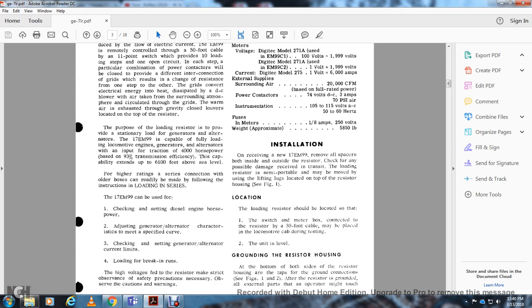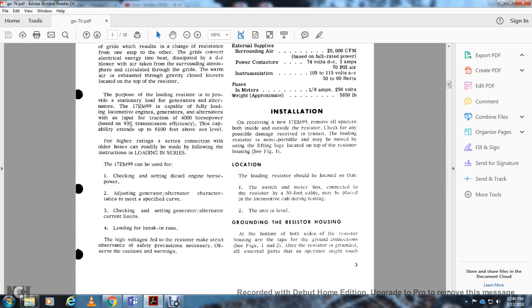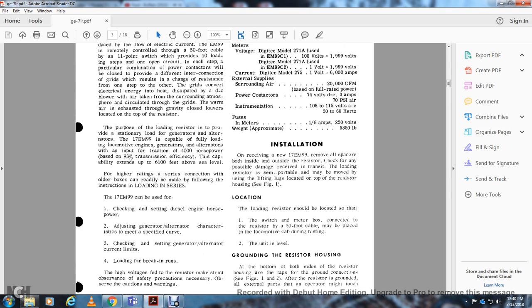The 17EM99 can be used for checking and setting diesel engine horsepower, adjusting generator alternator characteristics to meet the specified curve, checking and setting the generator alternator currents, and loading for break-in runs. High voltage is fed to the resistor. Make strict observance of safety precautions necessary. Observe the cautions and warnings.